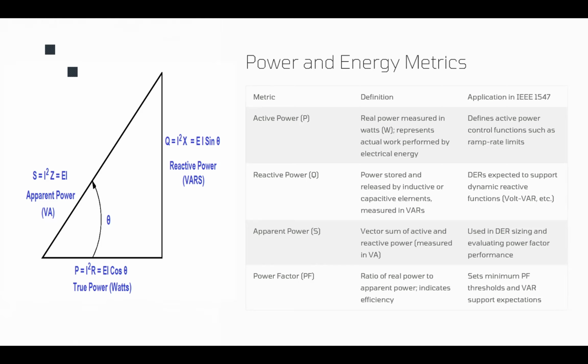Now, IEEE 1547 defines the real power control functions, so it can apply those requirements to address the challenges that we mentioned. We could have ramp rate limits that control how fast the DER output can change. Or we could have a maximum power limit. By power, I mean active power, which caps the DER output so we could avoid reverse flow and feeder overvoltage. Or we can have a volt-watt mode, which automatically reduces the active power output when the generation is more than the demand. So again, we could avoid feeder voltage rise and reverse power flow.